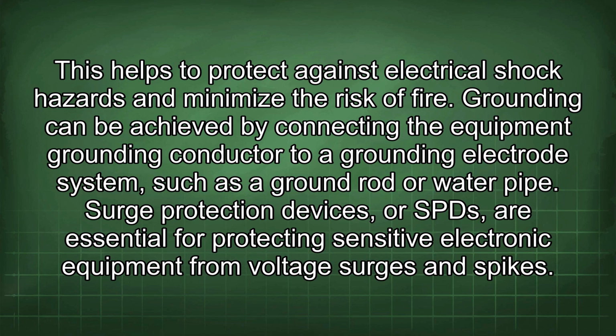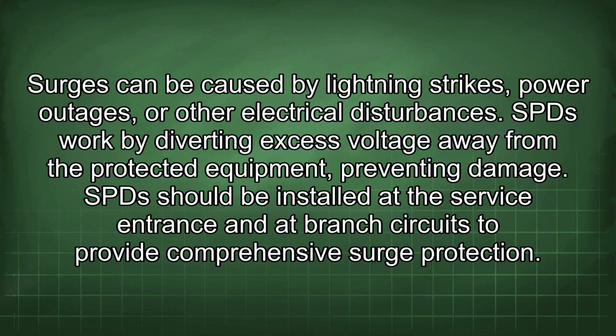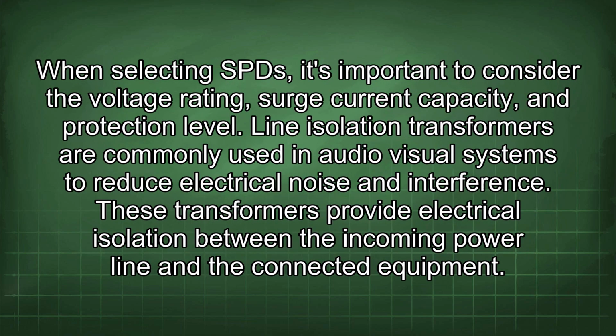Grounding can be achieved by connecting the equipment grounding conductor to a grounding electrode system such as a ground rod or water pipe. Surge protection devices, or SPDs, are essential for protecting sensitive electronic equipment from voltage surges and spikes. Surges can be caused by lightning strikes, power outages, or other electrical disturbances. SPDs work by diverting excess voltage away from the protected equipment, preventing damage. SPDs should be installed at the service entrance and at branch circuits to provide comprehensive surge protection. When selecting SPDs, it's important to consider the voltage rating, surge current capacity, and protection level.